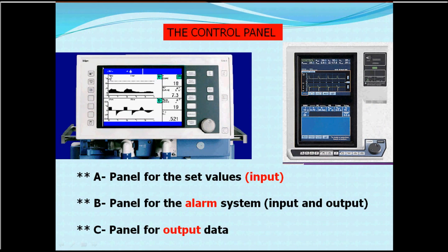This panel is composed of three parts. The first is the panel for set values — you set certain values, whether control variables, phase variables, or alarm data. The second is the alarm system, which is very important and should never be forgotten. Most doctors or therapists unfortunately tend to forget the alarm settings when managing a patient on the ventilator.